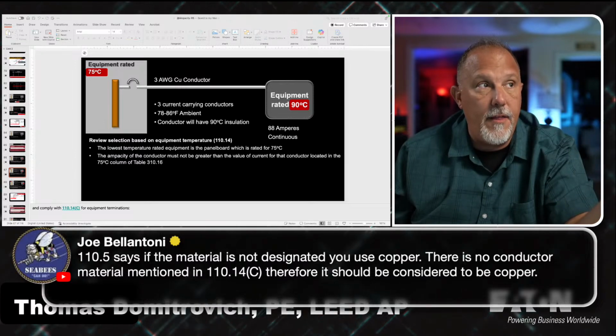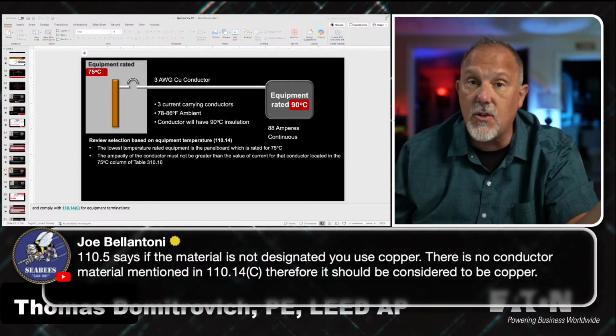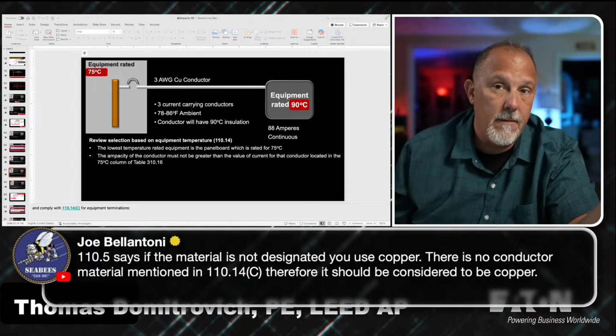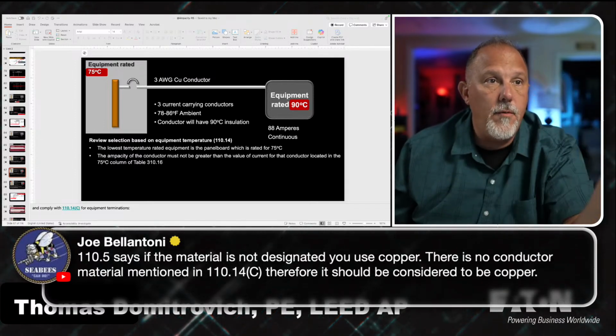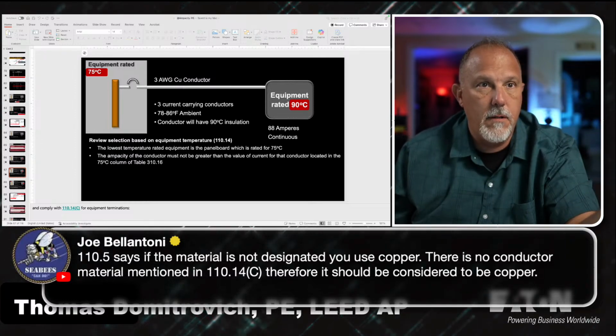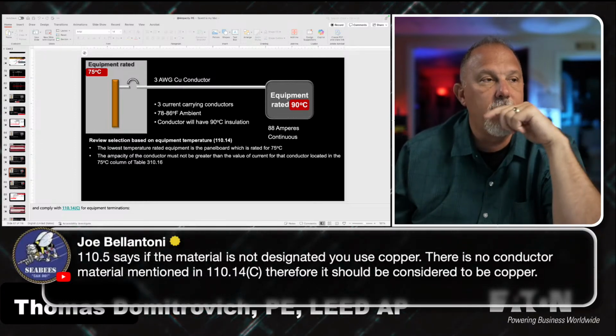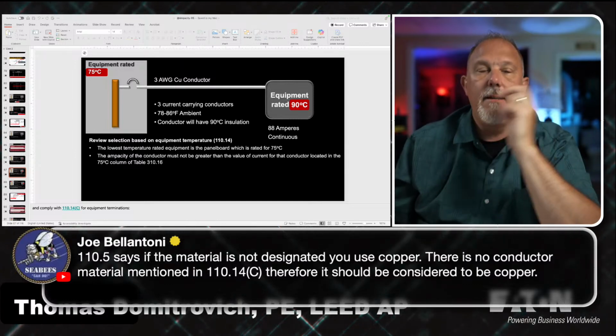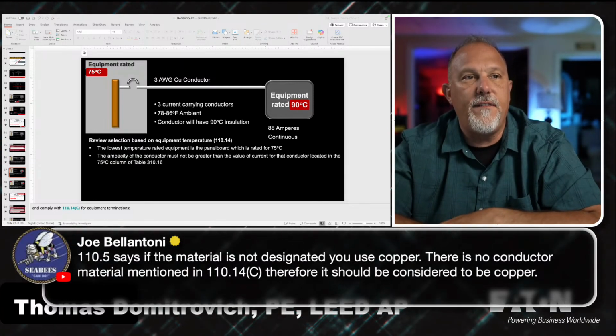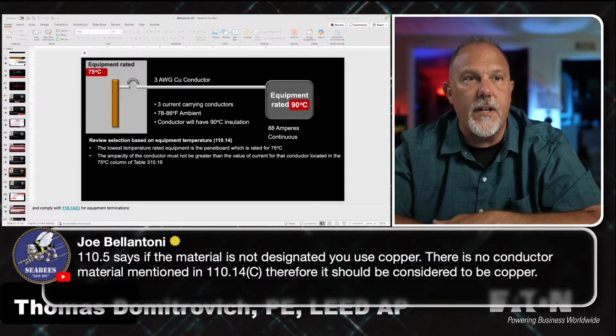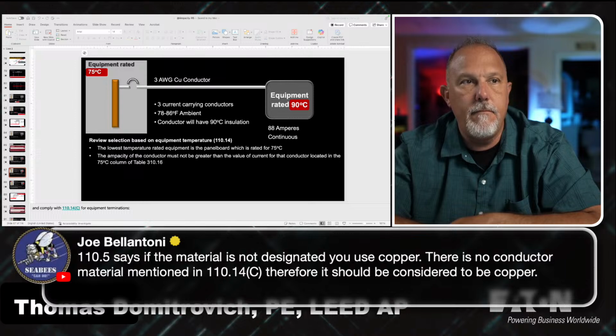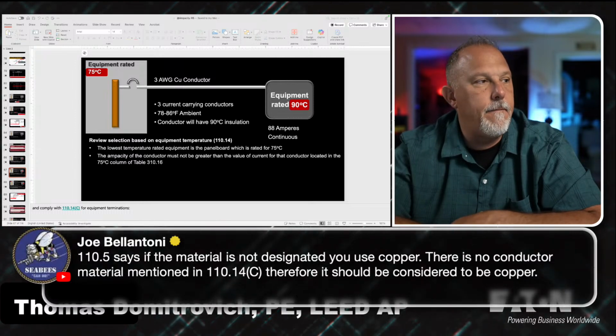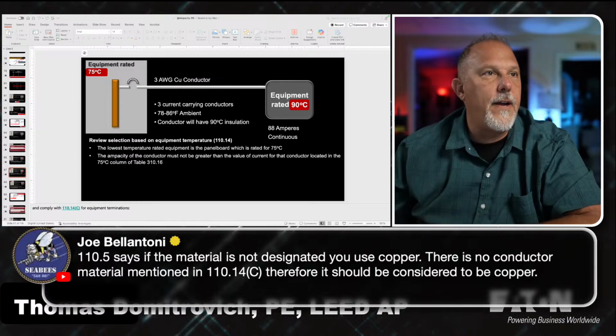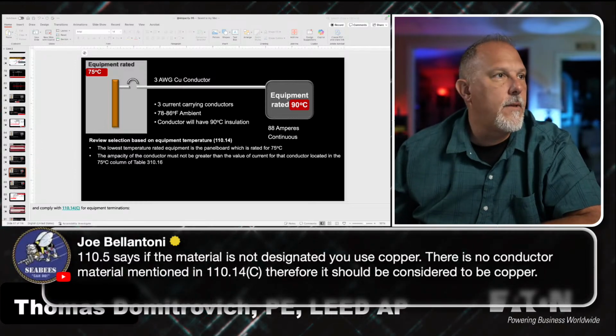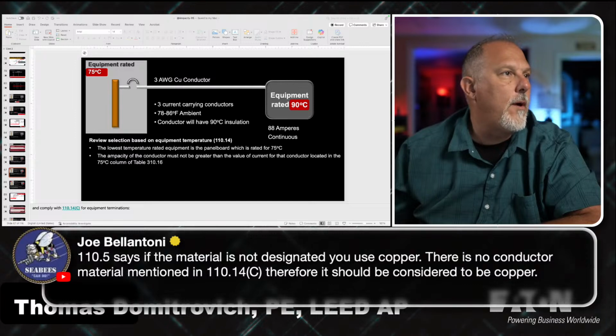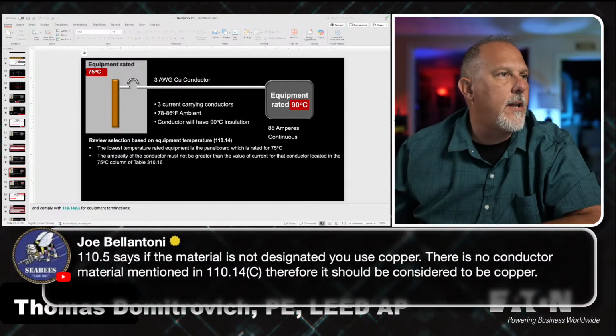So, Joe, does that mean that the requirements of 110.14(C) don't apply to aluminum? That's my issue. If it only applies to copper, but I think the adjustment, so I would have to look at a 14 copper and say, what's the equivalent copper clad aluminum, right? So if I look at a 14 copper, and man, what time is it? I got a hard stop at 1. If I look at copper, open a new tab.